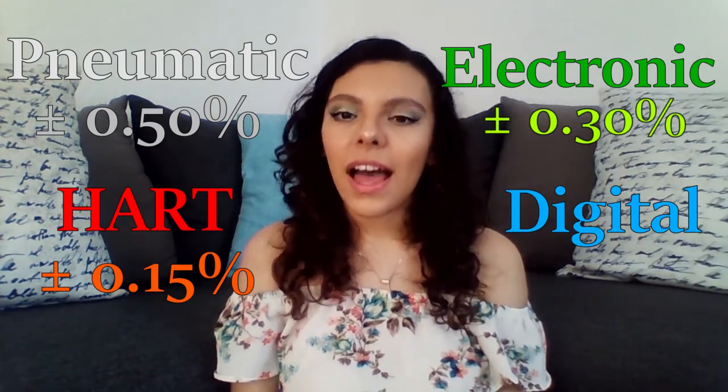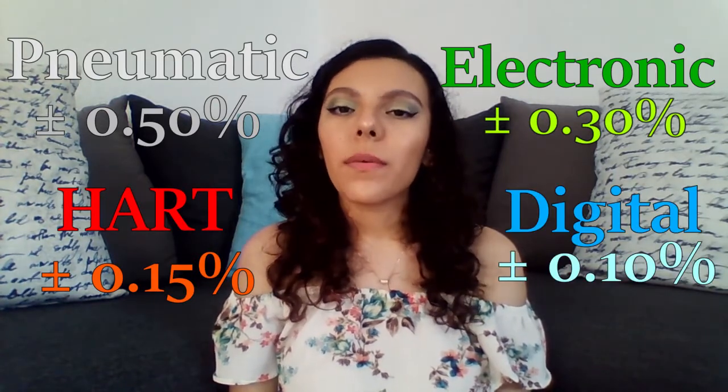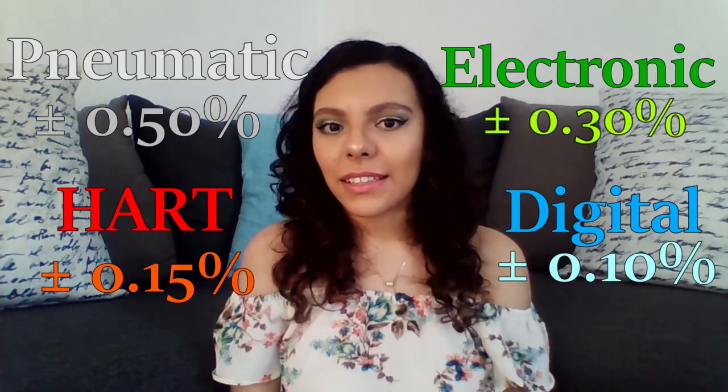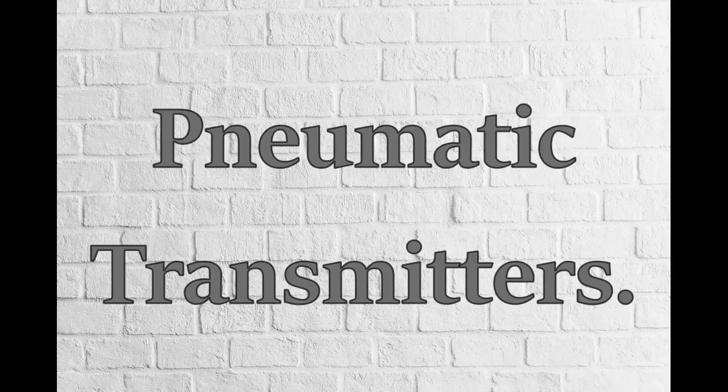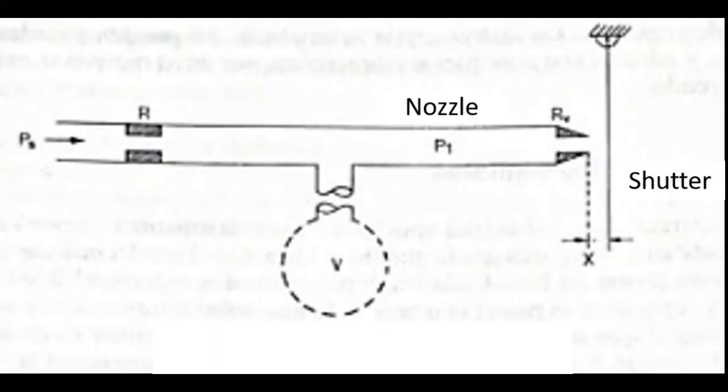and digital signals have ±0.10%. Remember that accuracy is measured in terms of inaccuracy. This type of pneumatic transmitter is based on a nozzle-flapper system that converts the movement of the primary measuring element into a 3 to 15 PSI pneumatic signal.